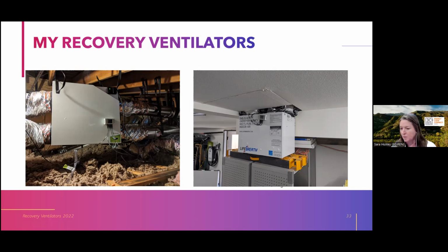And then Michelle just asked a question about that. How often do you change the filter and clean them when it's located in the attic? Well, it may be located in the attic, but all the air streams are not from the attic, so it doesn't get attic air. It's well sealed. But I get up there every 6 months at the latest, and every quarter as a best practice. And I find that most of the time the filter is reasonable in that window. The one on the right had a bug infestation last time I did it. I shouldn't say an infestation, but where our particular port was, it had sucked in a few mosquitoes and stuff. And so I just had to vacuum those out. And that's why you have to do it periodically.